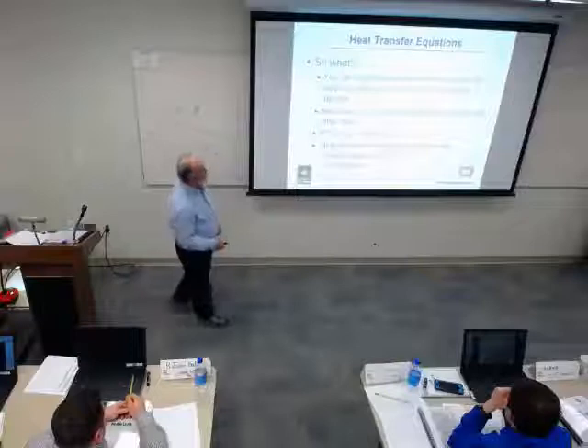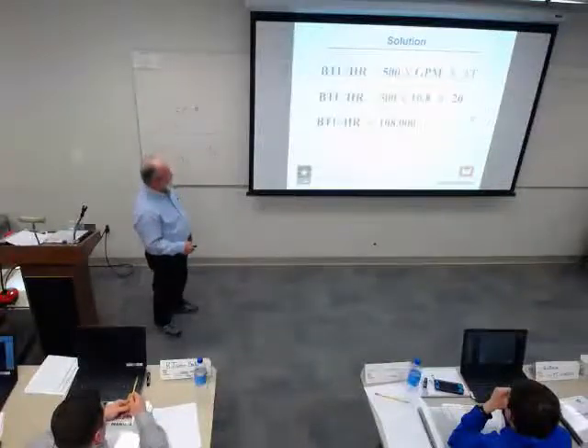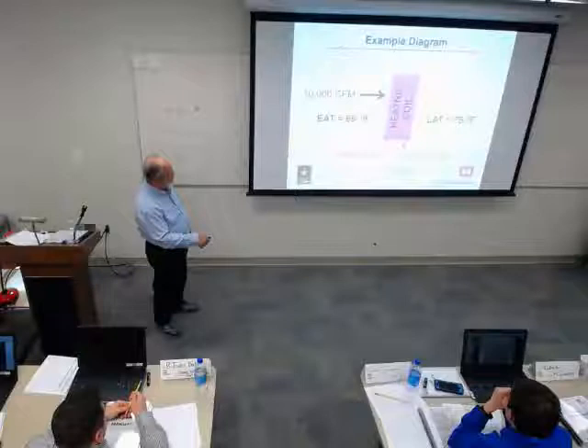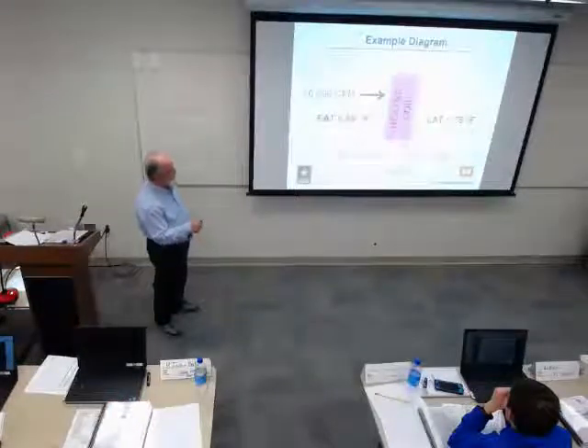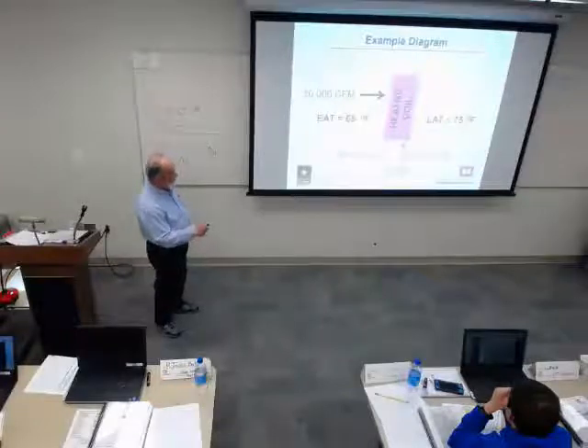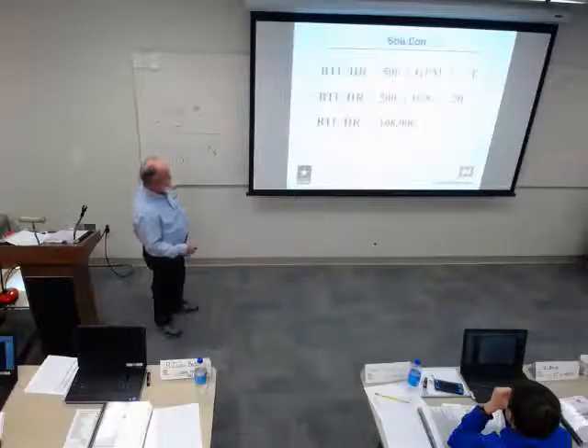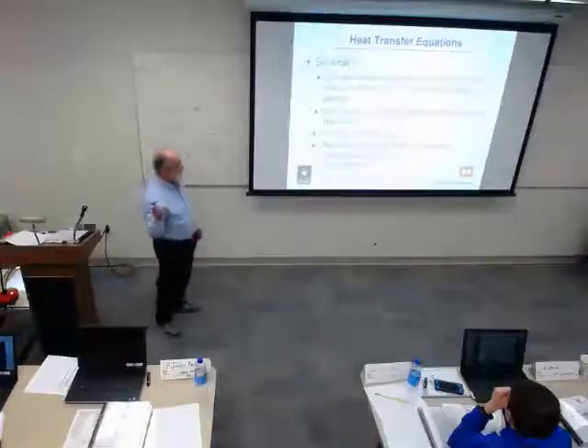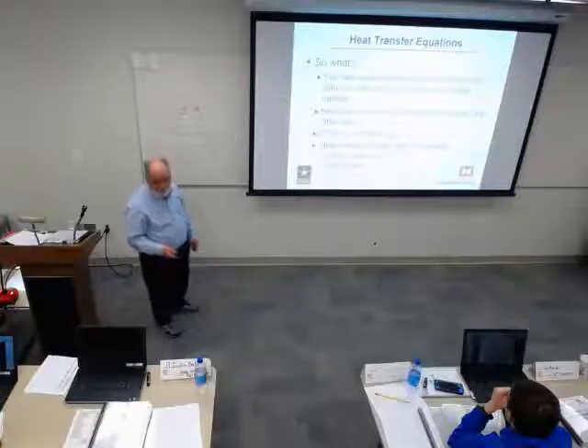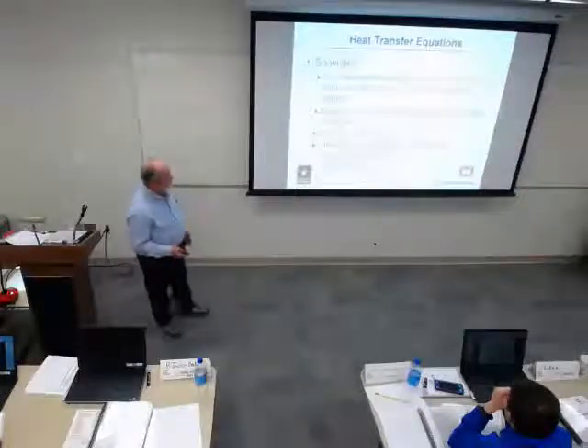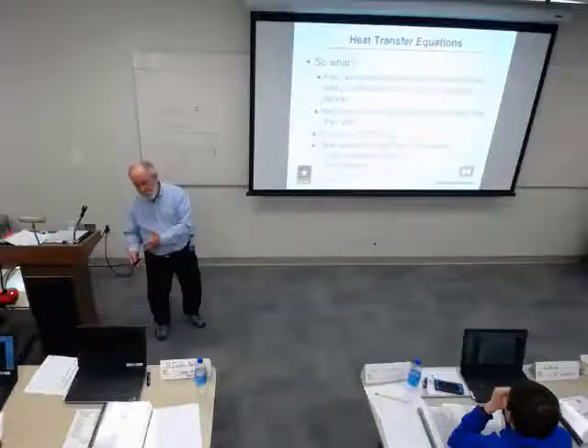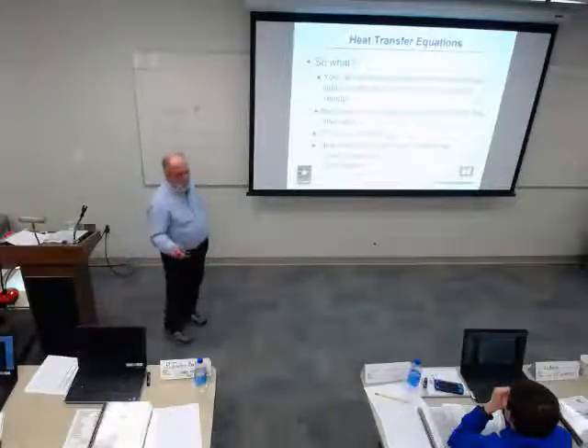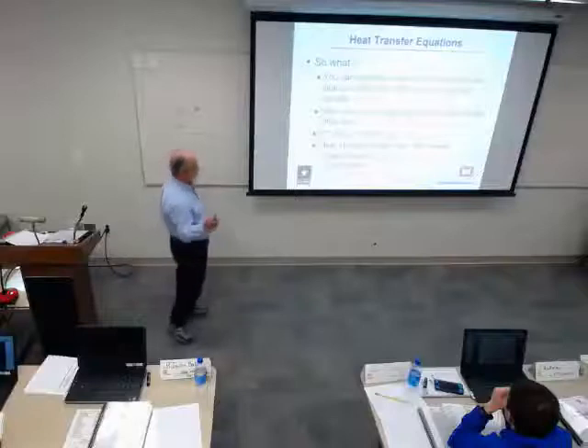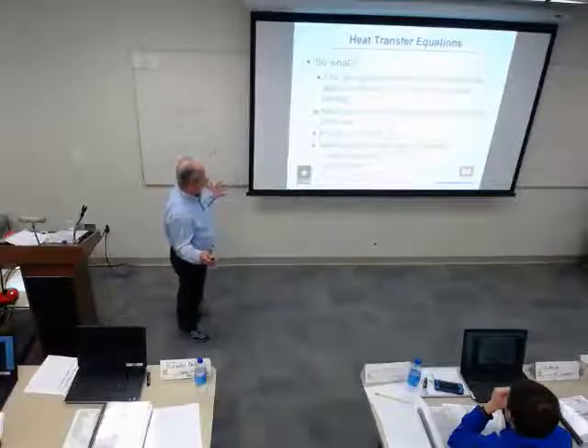So we can compare the water side. Well, let me just go back up a little bit. We've already done the calc up here for the air, so we know how to calculate the energy that's transferred on the air side. And now we're looking at the water side. What that allows us to do is to look at the two and compare them. It should be the same. Everything that came out of the water should go into the air. Or if it's cooling, everything that came out of the air should go into the water. Regardless, the heat loss should be the same on both sides of the tube.